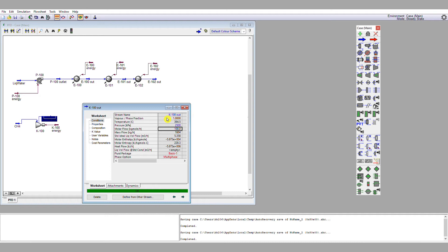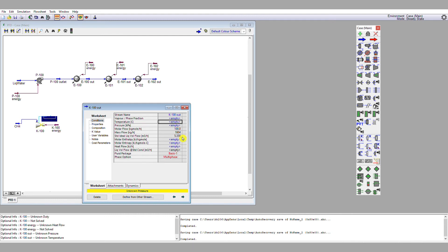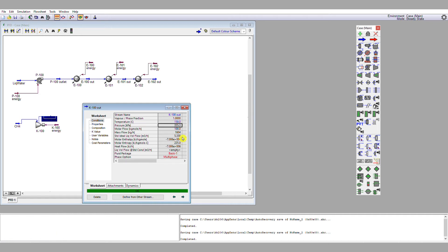Herein lies the problem — don't treat a process simulator as a video game; you have to keep tabs on reality. You would never have a compressor running that hot, especially with a flammable gas. The outlet temperature of compressors is typically limited to very roughly 140 to 150 degrees C, due to how you lubricate the bearings in these large pieces of rotational or reciprocating machinery. So what you will almost always find are multi-stage compressors: one stage limited by its upper operating temperature of around 150°C, followed by an intercooler, and then a further compression stage. I'm going to put an upper temperature specification of 150 degrees C, and that takes methane from 1 bar to 3.5 bar.